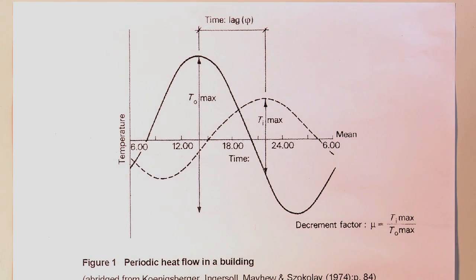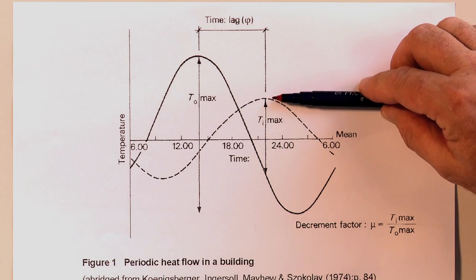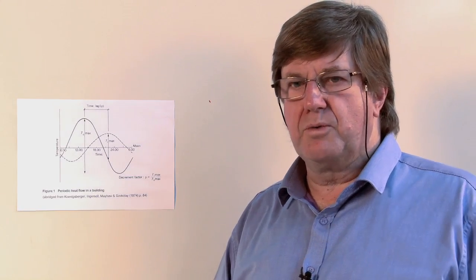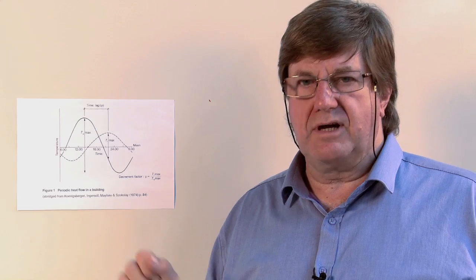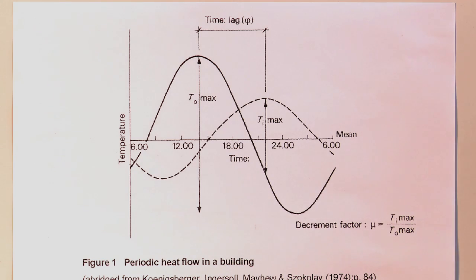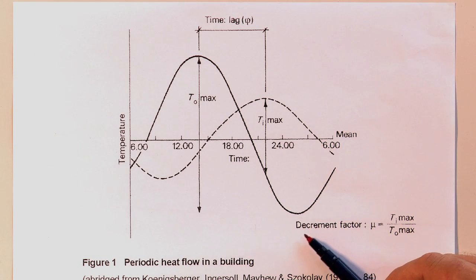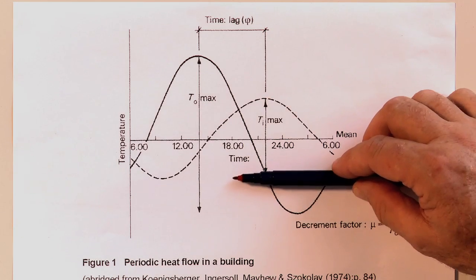We also need to note that there is a temperature drop — from here to here. We can expect that, because we have a lot of energy lost travelling through the brick wall, a lot of energy lost through the 40mm air gap, and further temperature lost through the gyprock wall. The term we use to represent this is the decrement factor.